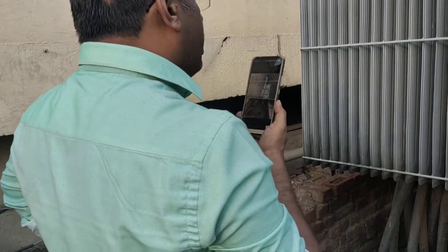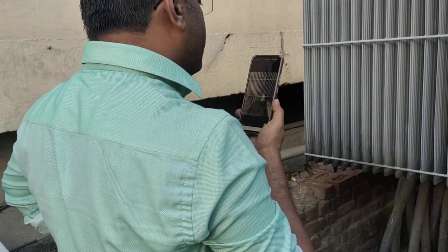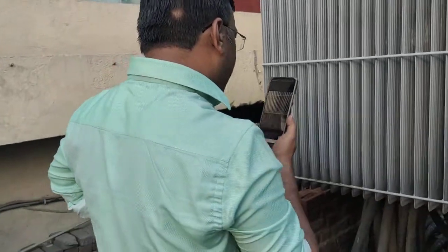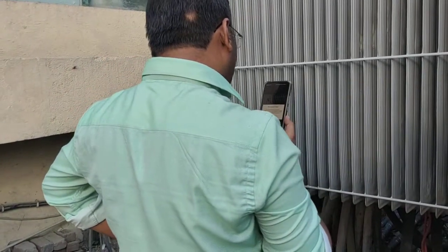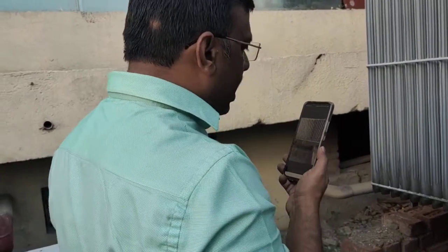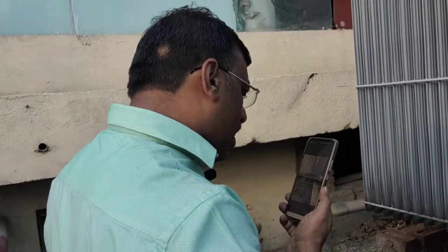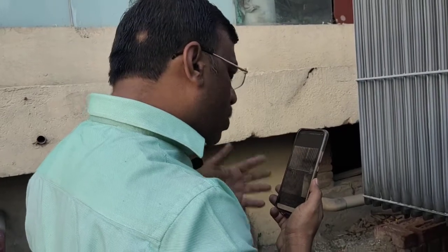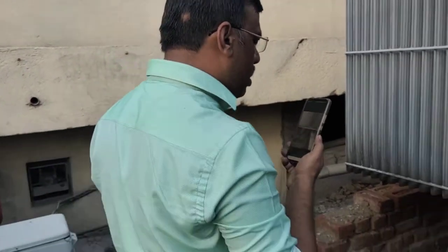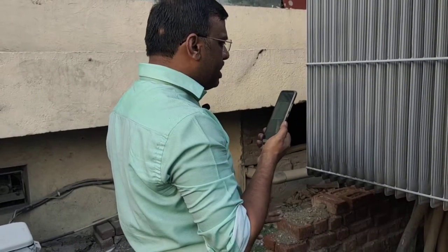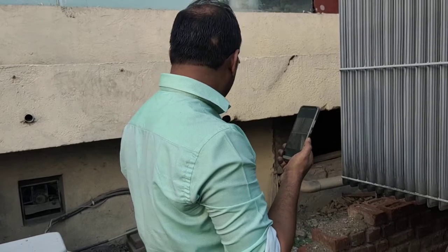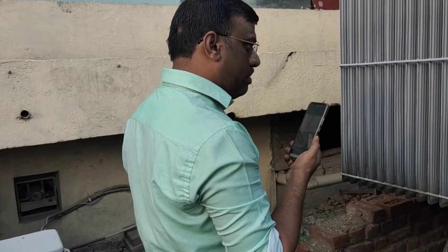It's almost 3 meters, 3.5 meters. It depends upon the soil. If you have sandy soil or rocky soil, then you go for chemical earthing. If you have muddy soil, you can go up to 10 feet or 12 feet, which is the standard. But 3 meters is the minimum. Is it okay?